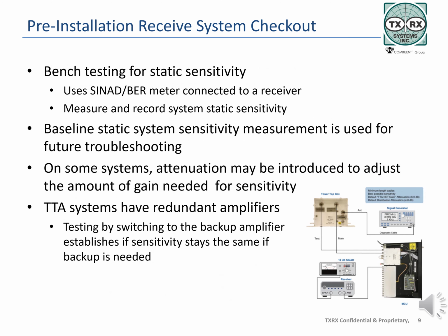Follow the steps outlined in the operations manual and connect a signal generator, SINAD or bit error rate meter, and a system receiver. Perform the static sensitivity measurement for the TTA system as outlined. Record the results, which can be used for future system troubleshooting by comparing new measurements against your original measurement. Remember that this will show static system sensitivity changes, pointing to faults that may have happened inside a system and not changes caused by interference or changes in noise levels outside the system.